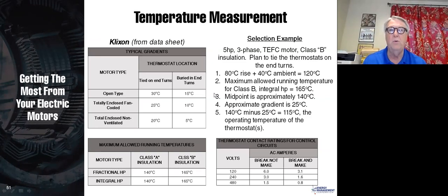But they will tell you what temperatures they recommend that you buy, and they're saying down here maximum allowable temperatures for an integral horsepower motor with Class B insulation is 165. Well, that's awfully hot. And so generally we would probably put that down much lower on the range of maybe 130. But this is what the Klixon data sheet says. And sometimes they put these a fair amount above the rated temperature because they don't want them to trip.